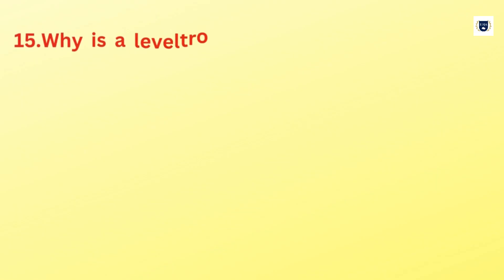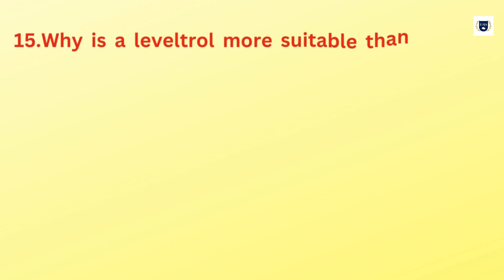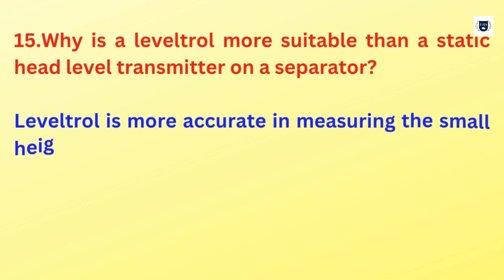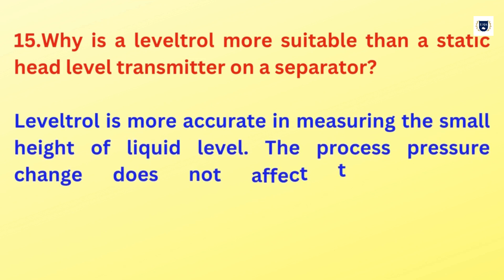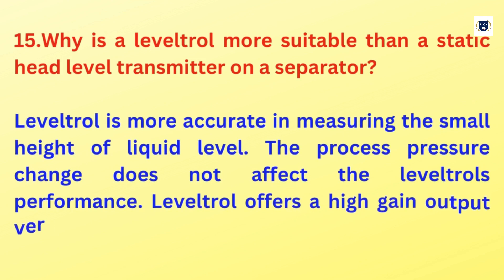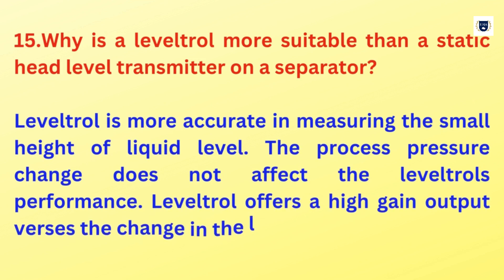Why is a Leveltrol more suitable than a static head level transmitter on a separator? A Leveltrol is more accurate in measuring the small height of liquid level. The process pressure change does not affect the Leveltrol's performance. The Leveltrol offers a high gain output versus the change in the liquid level.